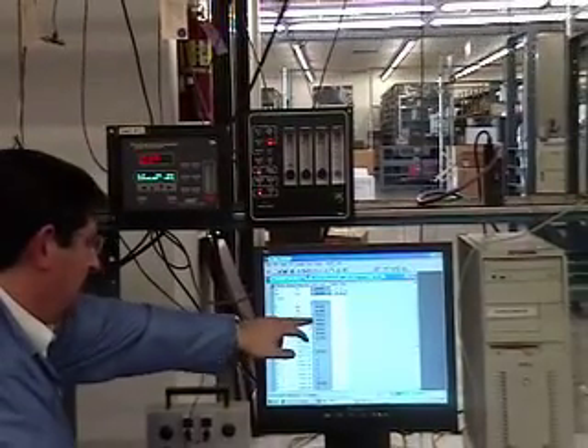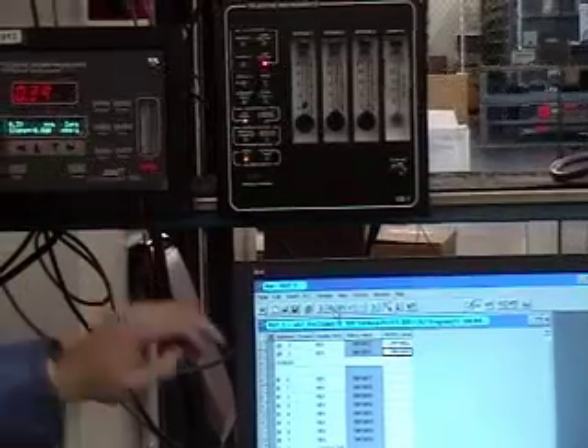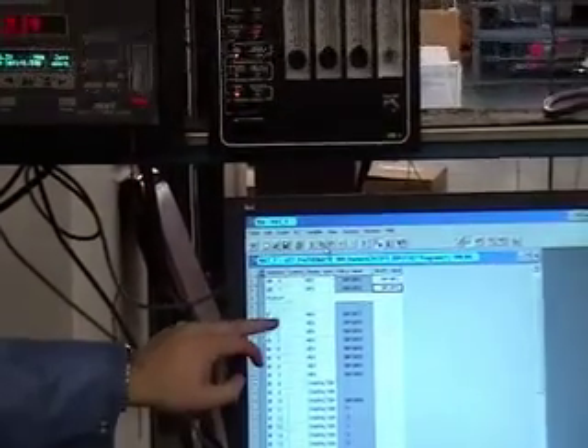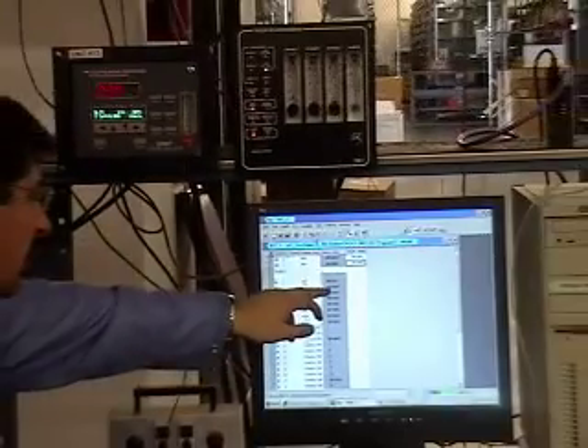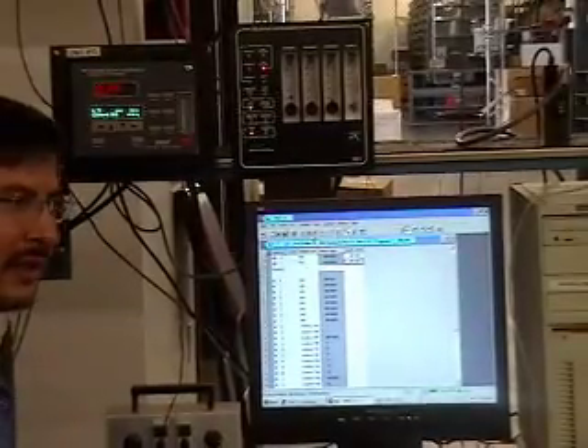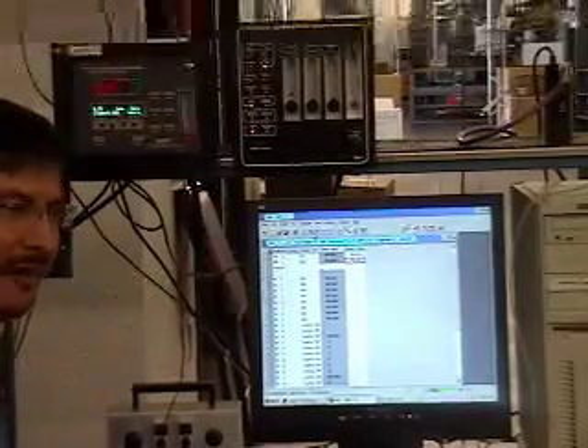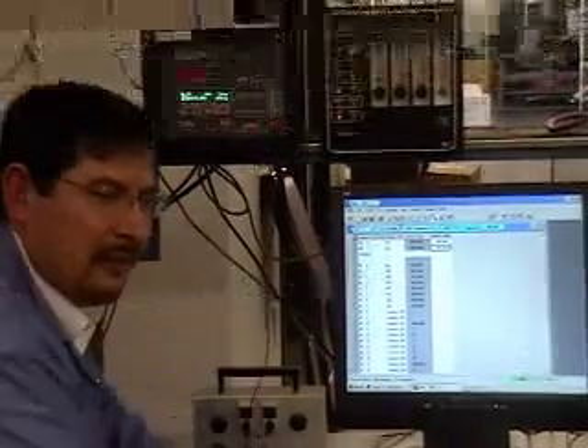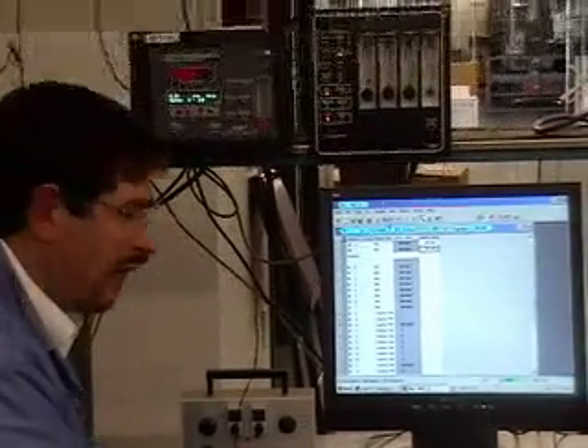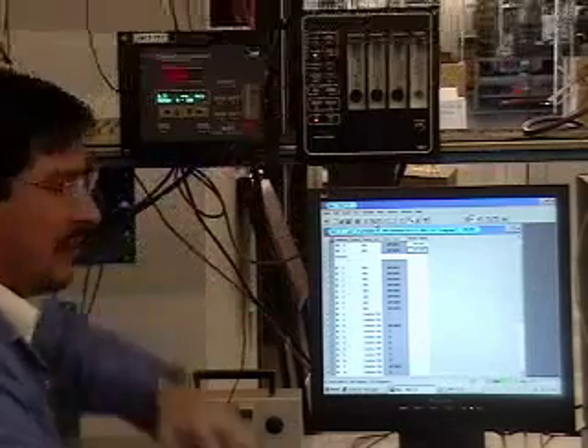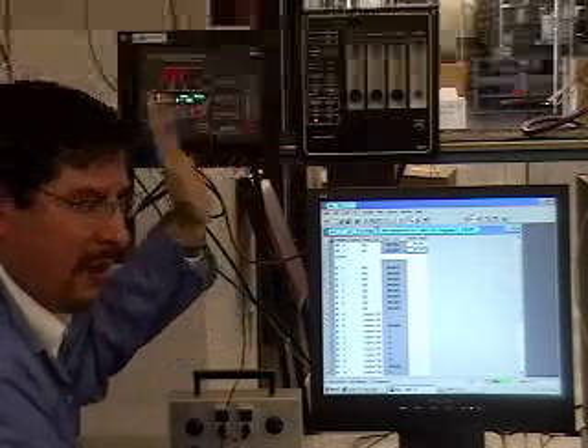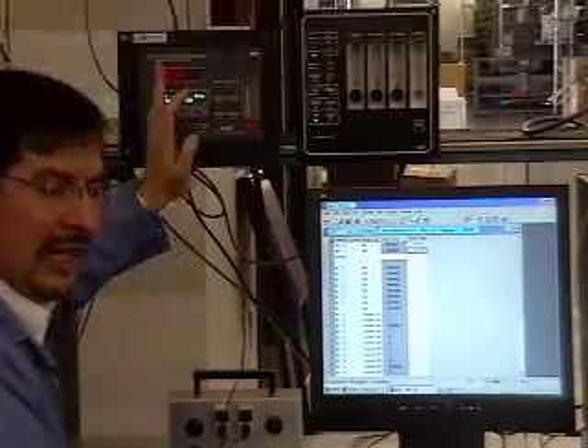The 4 to 20 milliamp output will be on the first 2 addresses. When it's RS-232, you use the first 4 addresses of the output here to check the concentration. When it's only 4 to 20 milliamps, it's only the first 2. And it is a number that you divide by 100 to get what percentage of range output you have. If it's 4 milliamps, you get 0. If it's 20 milliamps, you'll get a number that will give you close to 100% full scale. Okay, so it's 0 in return. So that's how you operate the different modes of operation for this BB1 and analyzers like the 3000 TA. Okay, thank you very much.